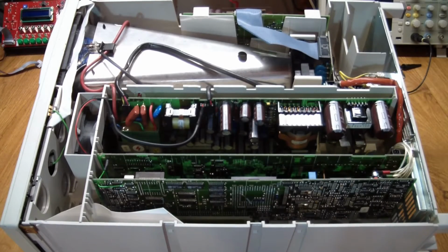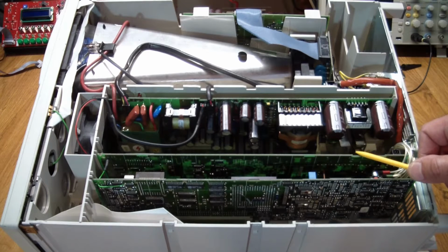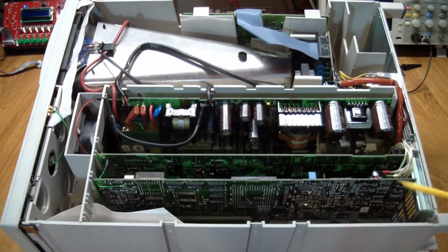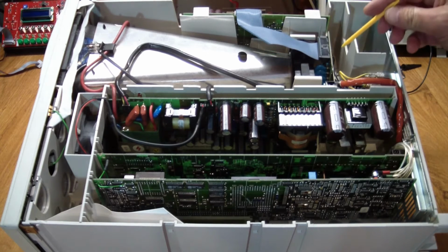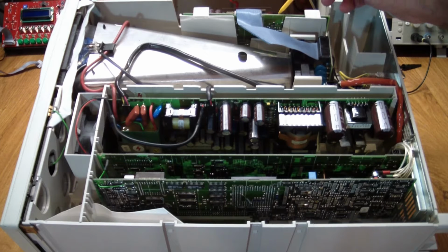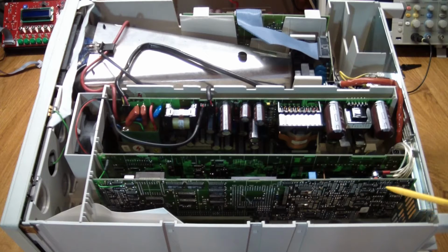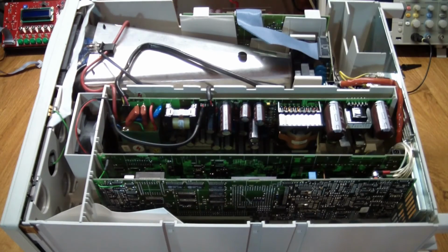So here's the top of the instrument with the cover taken off, and you can quickly see why this instrument is relatively light. That's because the case is made mostly of plastic. Quickly going through the components, we have the acquisition board here, the CPU board here, underneath it is the motherboard, the power supply, which generates all the voltages, including the high voltage, directly on here. We have the tube and the neck board. We have the video or the screen driver board over here. And here's the fan, and here's the light bulb that is used for graticule illumination.